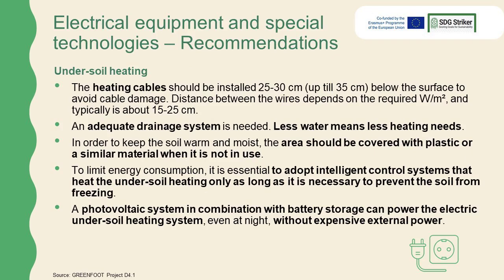Recommendations for undersoil heating are that the heating cables should be installed 25 to 30 centimeters below the surface to avoid cable damage. Distance between the wires depends on the required watt per square meter, and typically is about 15 to 25 centimeters. An adequate drainage system is needed. Less water means less heating needs. In order to keep the soil warm and moist, the area should be covered with plastic or a similar material when it is not in use.